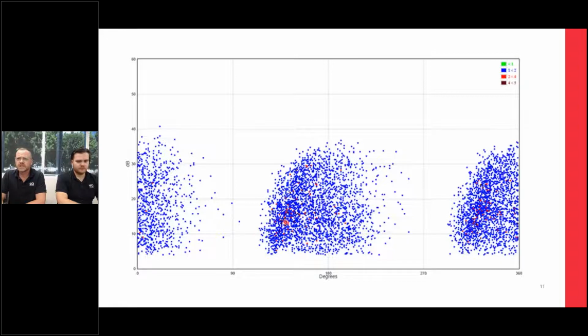Now, each of these dots occurs over time, and it is the signals given off by PD activity. Whether that signal is a sound, this is why I was explaining everything before. If we are listening to a sound, the instrument knows the amplitude of that sound, and the instrument knows where that event occurred in relation to the sine wave.